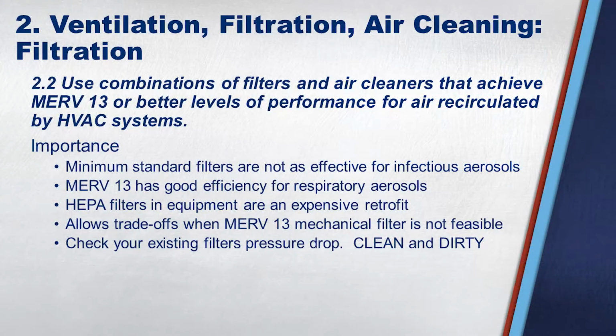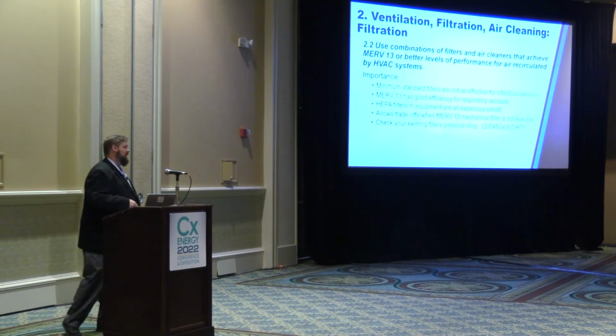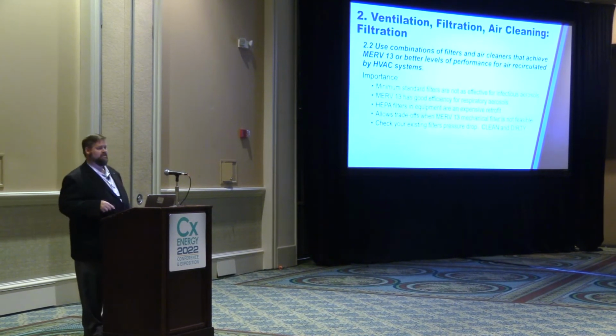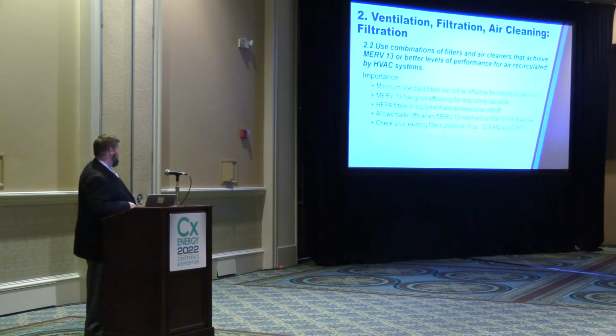So at the end of the day, no-brainer: code minimum. Then you get into a combination of filters and air cleaners to achieve MERV 13 or better. This isn't meant to say it has to be MERV 13—it's really meant to be a combination of different things, because you have different ages and types of equipment, and some equipment can't have those MERV 13 filters. They just don't have the availability to get the air through.